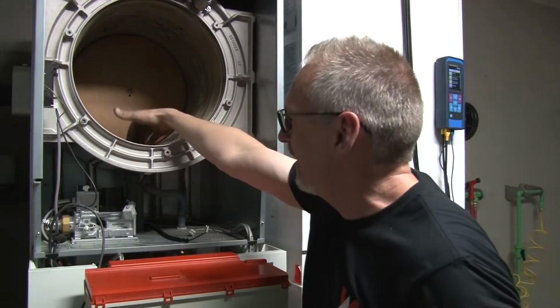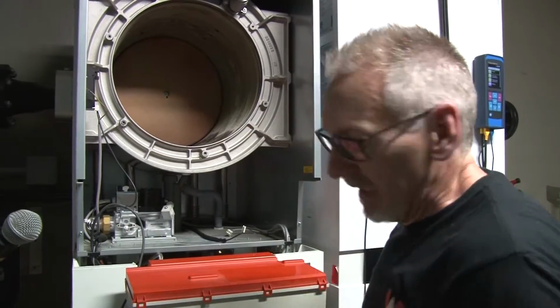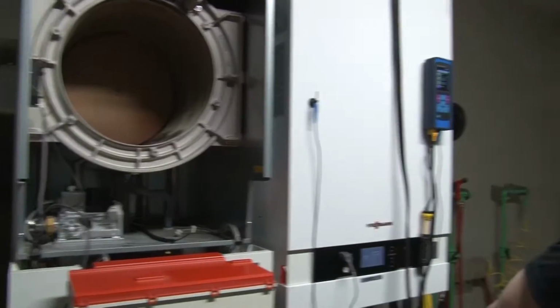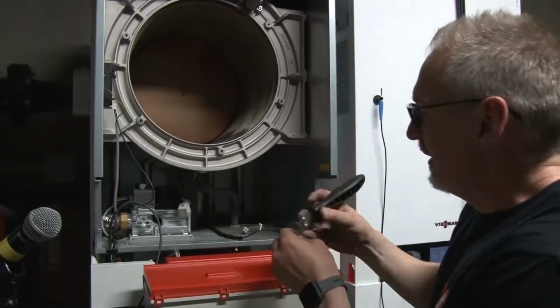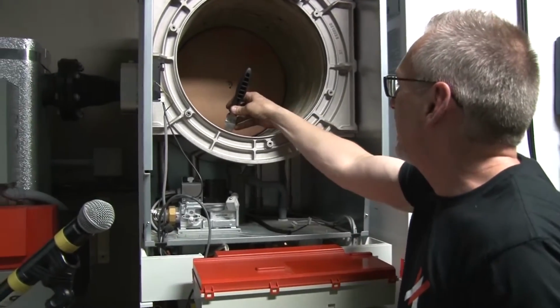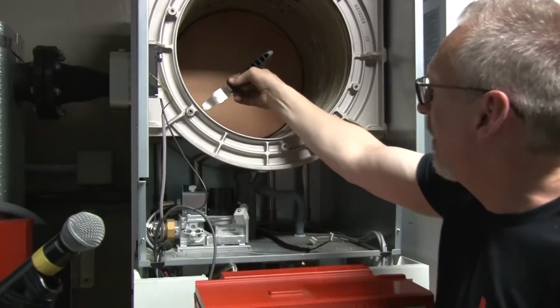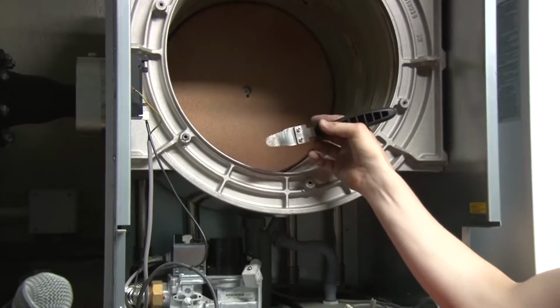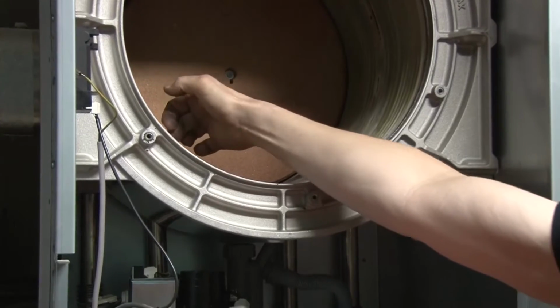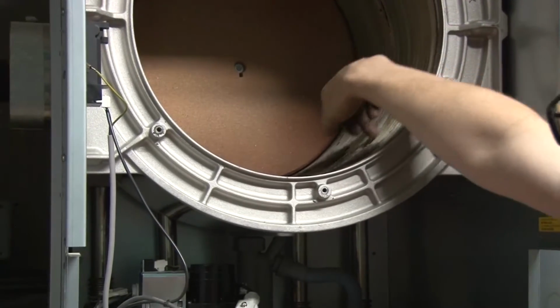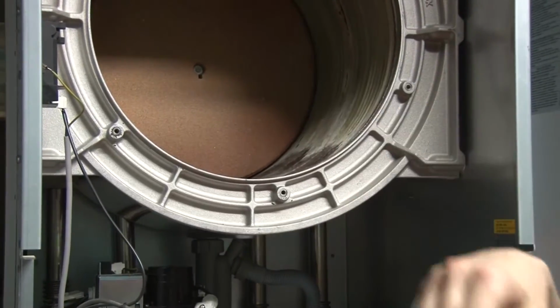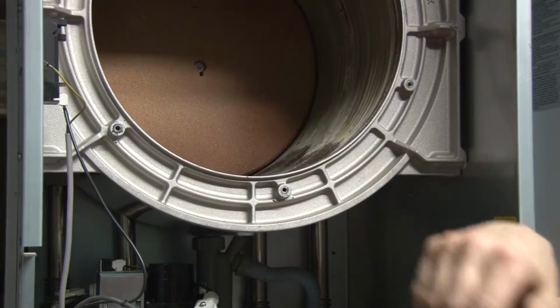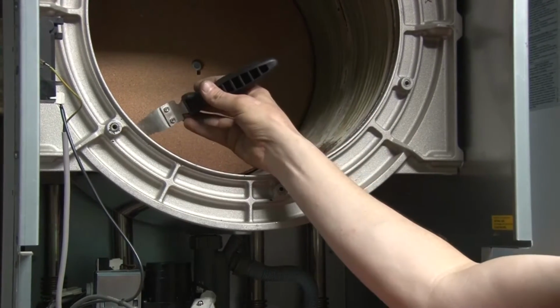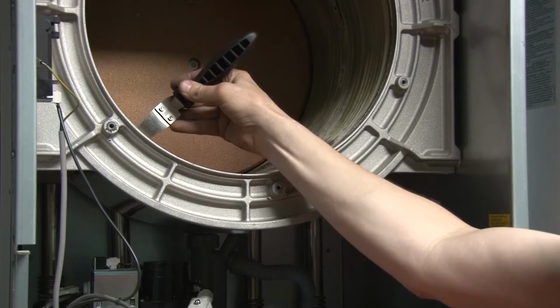That's getting into these flue gas passageways, and we've got a special little knife that we can use for this application. If I look at that tide mark, you can see where the debris was sitting. You can see the dark staining on the heat exchanger. Most of that's going to come off after we do the service here, but it's a really good guide as to where we need to address.